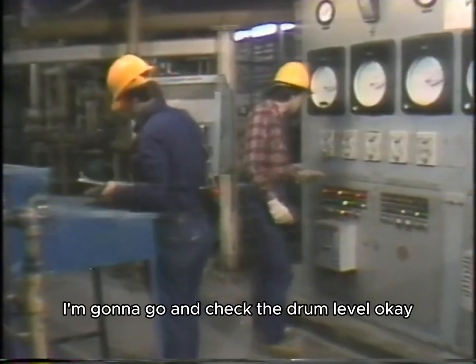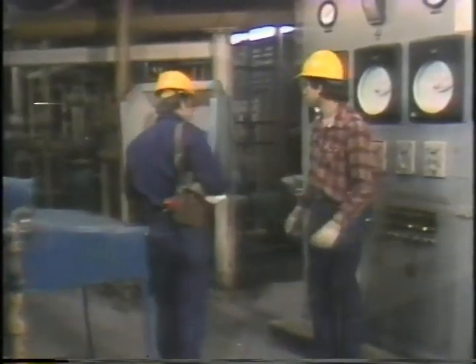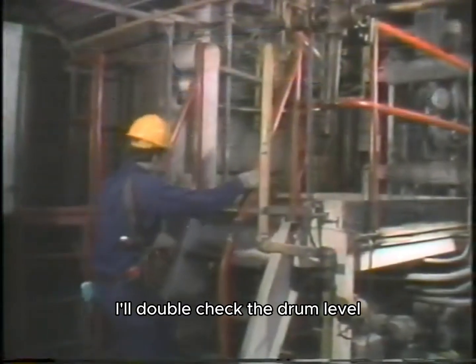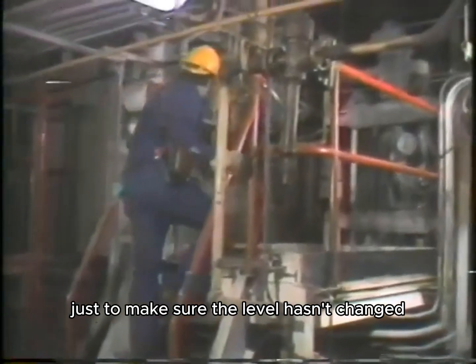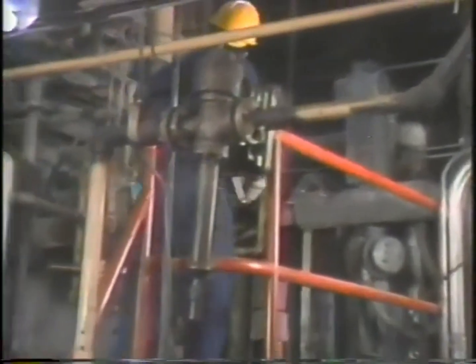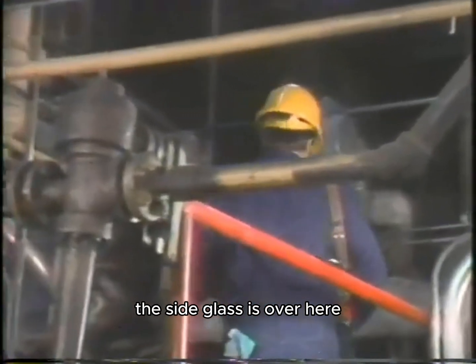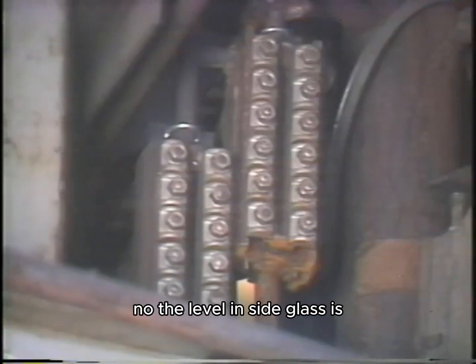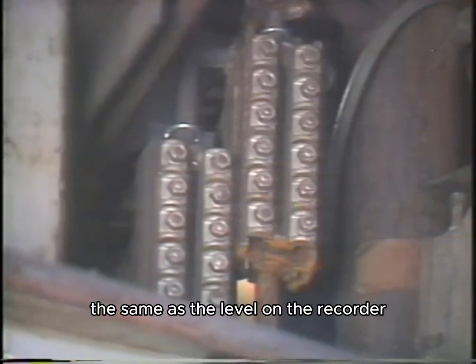I'm going to go up and check the drum level. Okay. I'll double check the drum level by looking at the sight glass just to make sure the level hasn't changed. The sight glass is over here. No, the level in the sight glass is the same as the level on the recorder.